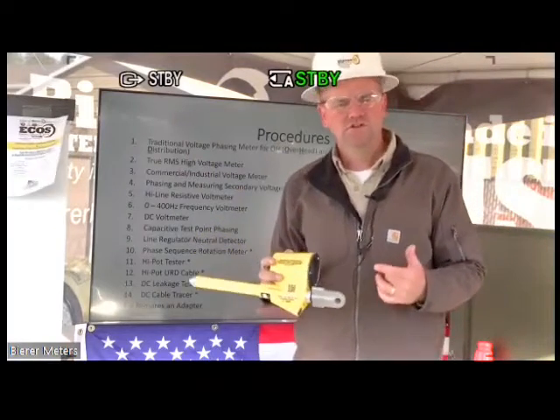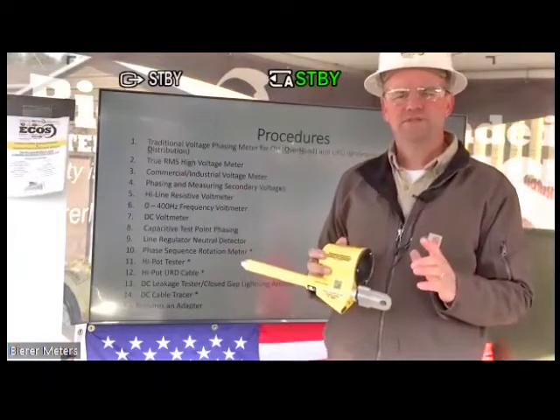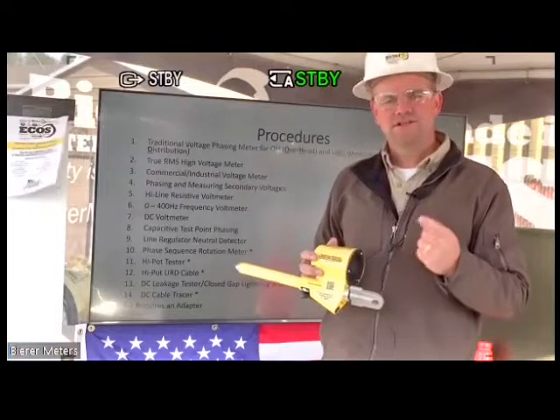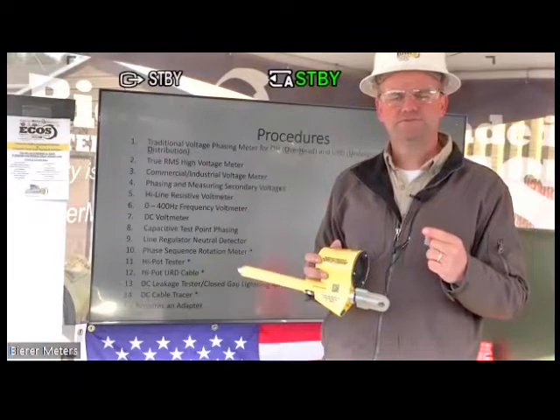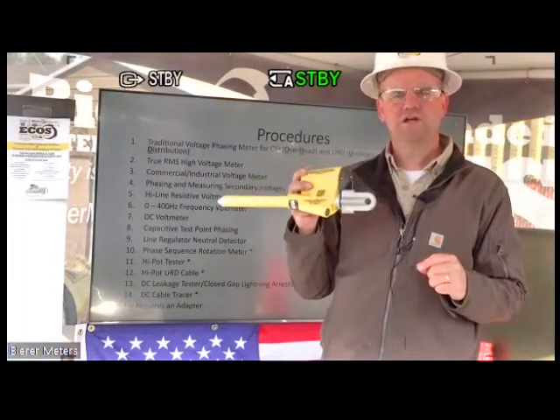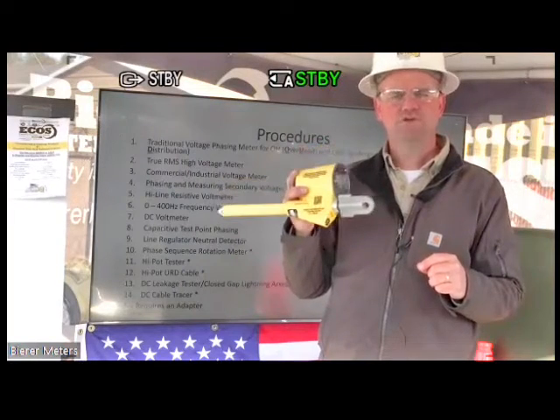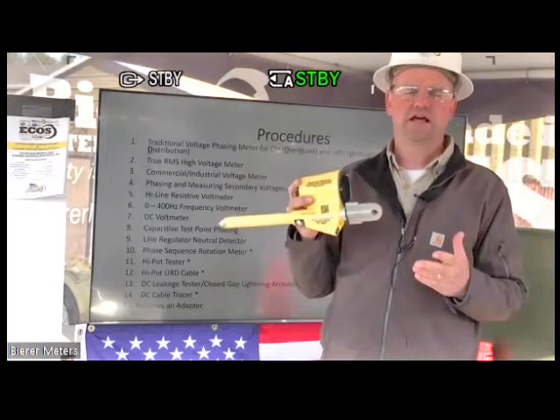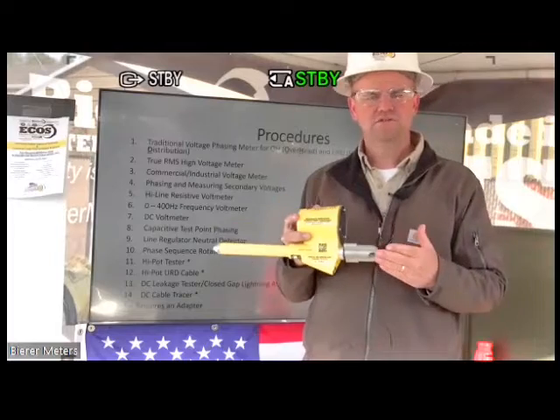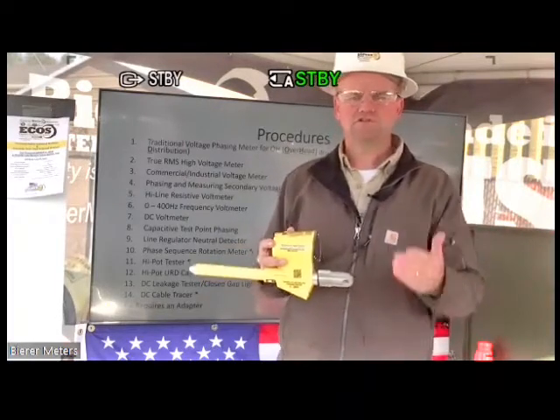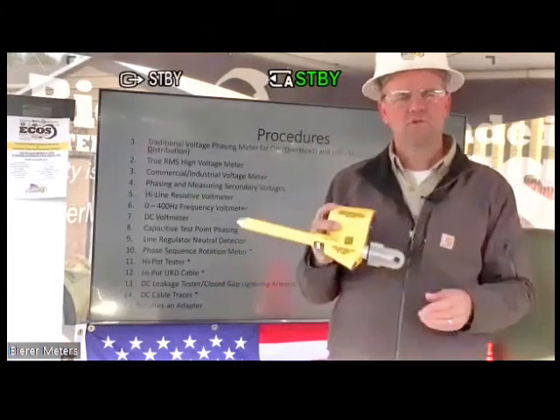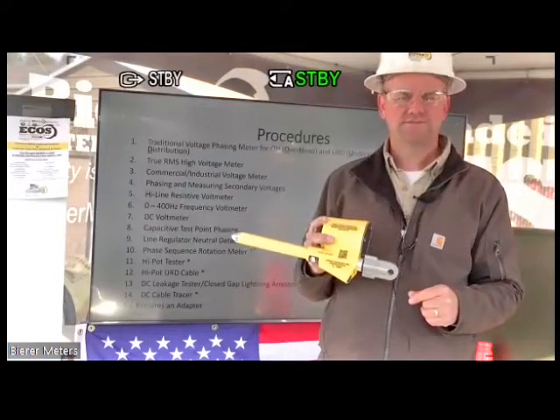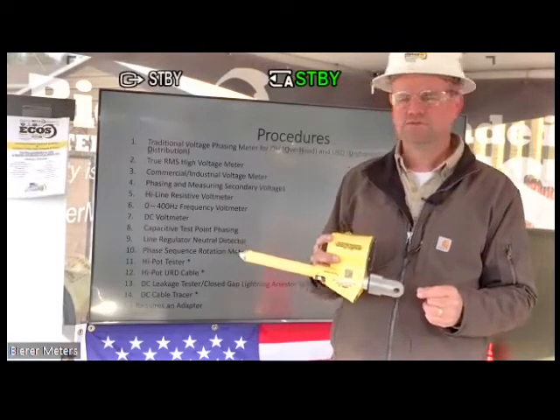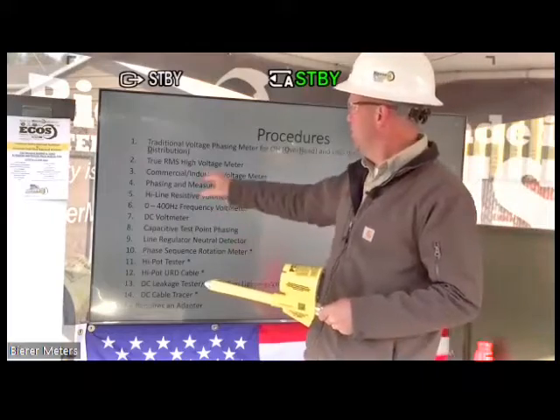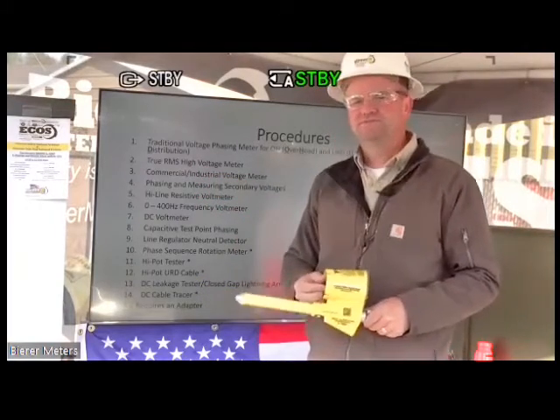In other words, if you're used to using a multimeter, like a Fluke multimeter, it says true RMS on that meter. Okay, this is a true RMS meter as well. So in other words, it's a high voltage Fluke meter. You can think of it like that. In other words, I can use it on secondary potentials or primary potentials, and a reading is going to be within 1% in the field. Okay, so commercial industrial voltage meter.